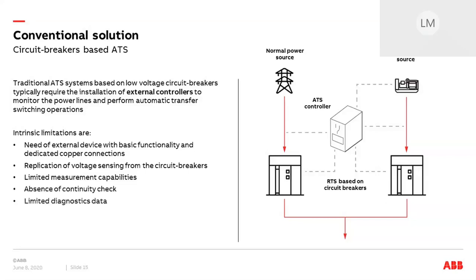The voltage sensing performed by the external ATS controller is in a certain way duplicated from the circuit breakers, which also offer wider measurement capabilities like currents and energy metering. In conventional solutions, reliability is also affected by the absence of continuity checks of internal and external connections, increasing the risk of unexpected failures. The limited diagnostics capability of the ATS controller significantly reduces effective and safe monitoring of the system. These traditional ATS systems also offer basic configuration without dedicated software tools and support only a few communication protocols like Modbus RTU.